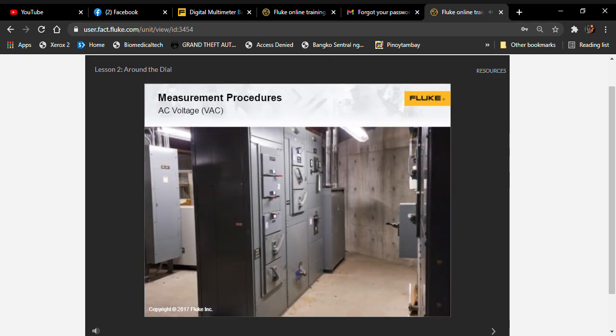The most common type of measurement is for AC voltage. Generally, multimeters are designed to measure voltages of 1000 volts or less. There are many typical levels of AC voltage within this range, from millivolts to 480 volts or more. When troubleshooting, you often need to measure voltage at multiple spots in a circuit.